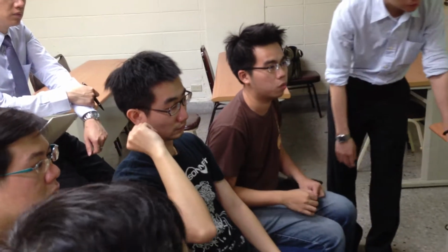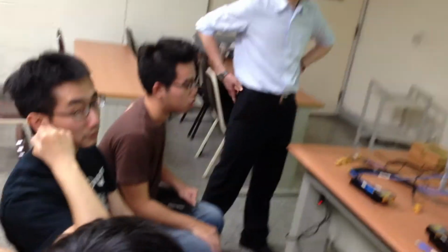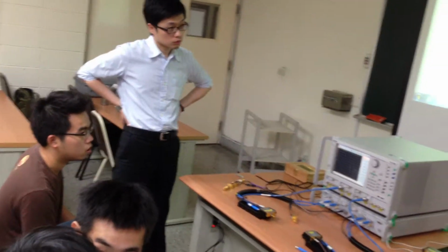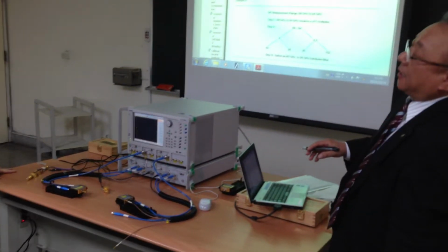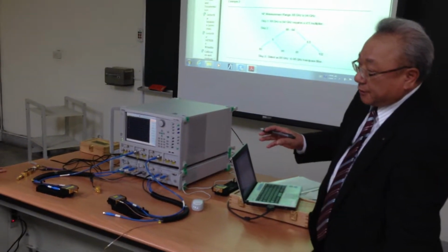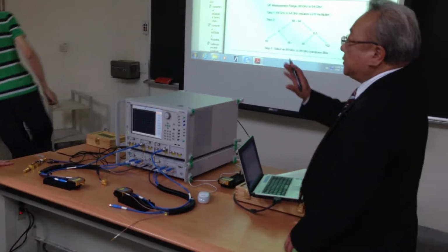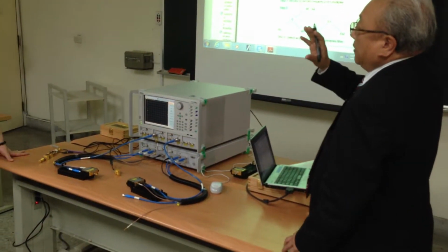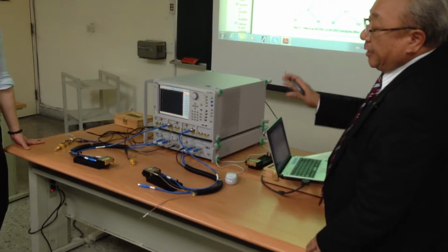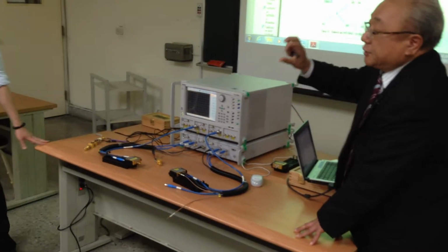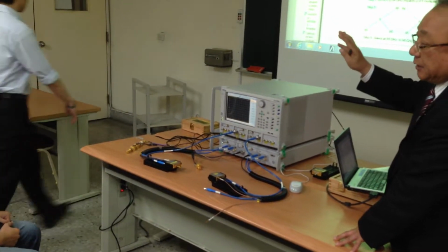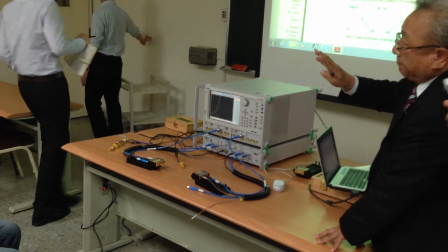How to measure the mixer's noise figure? Currently we do not have any user interface in the VNA. We can do that, but you have to set some of this measurement condition by yourself on the network analyzer, such as the mixer frequency and cables.